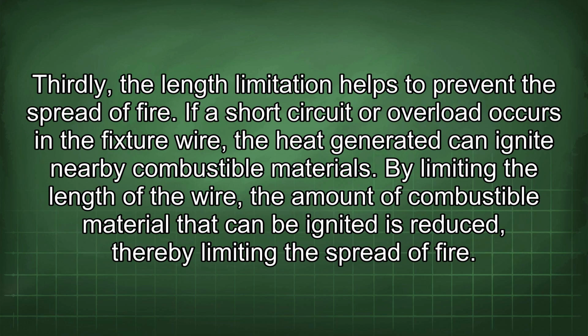Thirdly, the length limitation helps to prevent the spread of fire. If a short circuit or overload occurs in the fixture wire, the heat generated can ignite nearby combustible materials. By limiting the length of the wire, the amount of combustible material that can be ignited is reduced, thereby limiting the spread of fire.